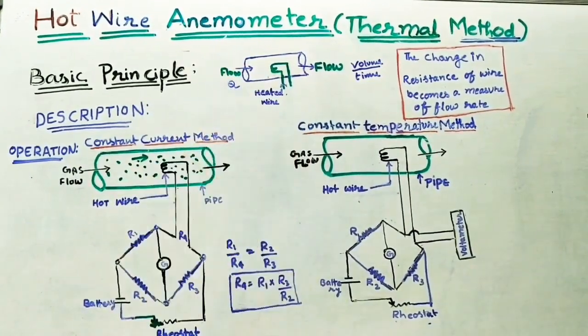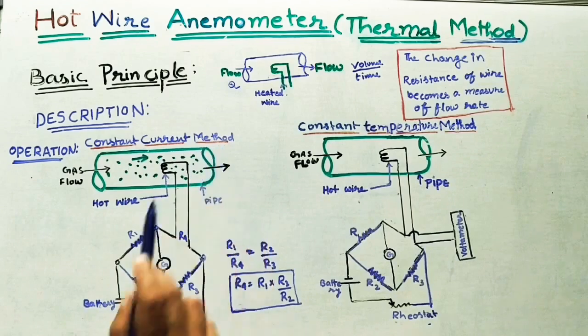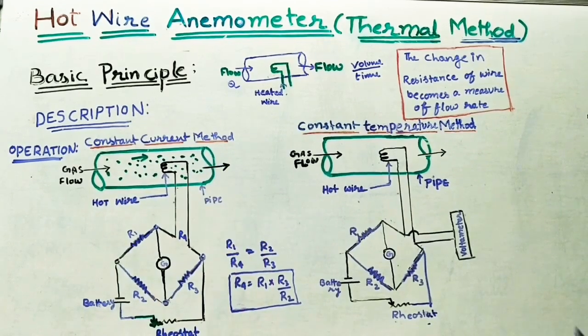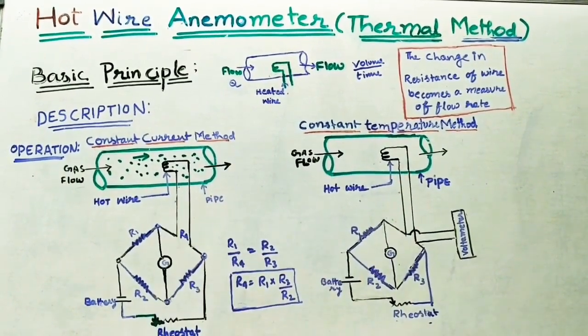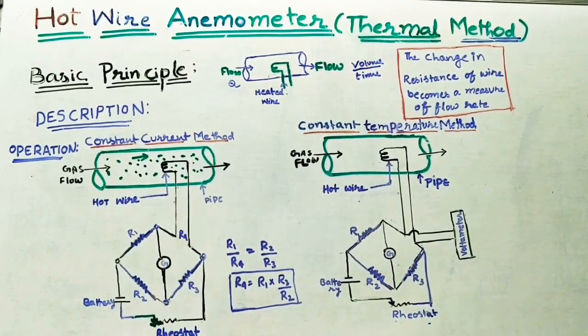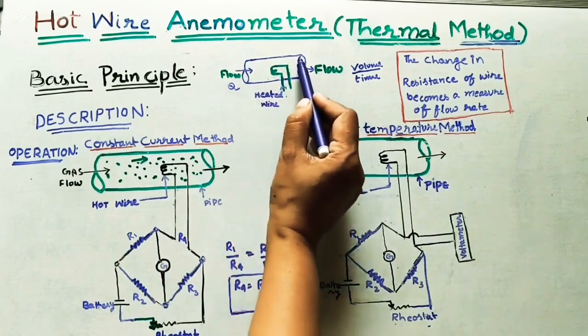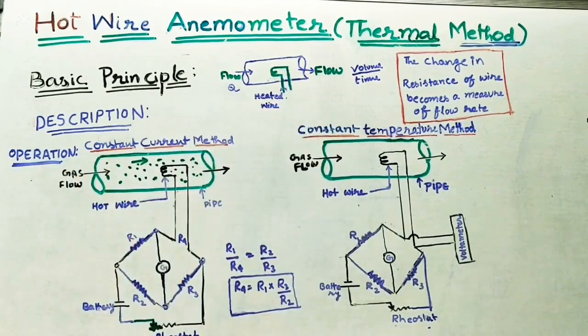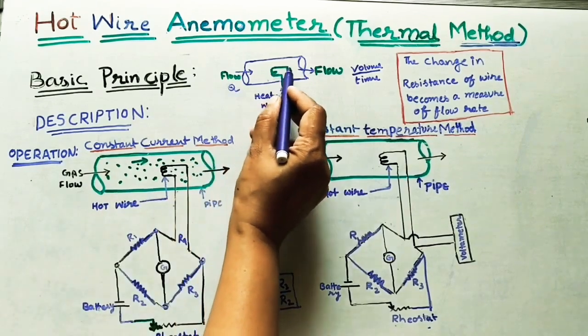So how will it find the discharge Q value? Here, what is the basic principle? We are using two methods: one is the constant current method and the next one is the constant temperature method. Both methods work on the same basic principle. I have drawn a diagram here. Flow is going in one direction at the input in a given pipe, and I am keeping one electric conductor — a heated wire — in the flow stream.